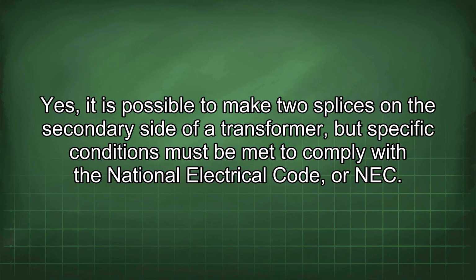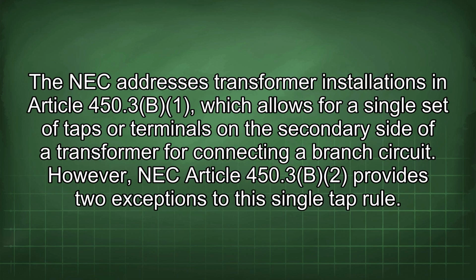Yes, it is possible to make two splices on the secondary side of a transformer, but specific conditions must be met to comply with the National Electrical Code, or NEC. The NEC addresses transformer installations in Article 450.3, which allows for a single set of taps or terminals on the secondary side of a transformer for connecting a branch circuit.